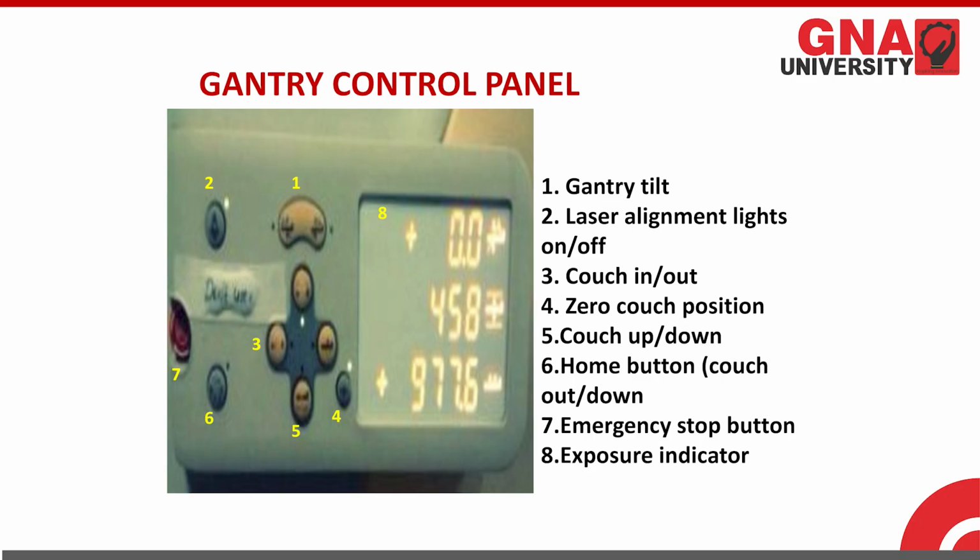Eighth, here onto these gantry controls, we have an exposure indicator which indicates the amount of exposure that was given to acquire a particular slice during the acquisition.